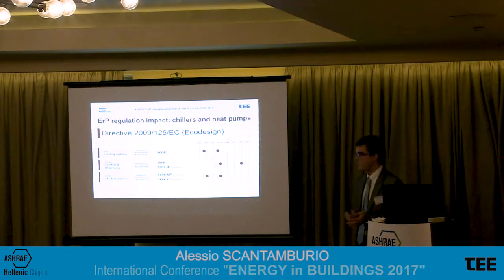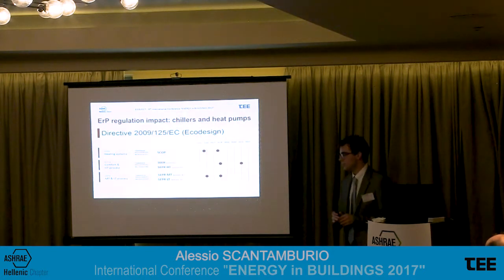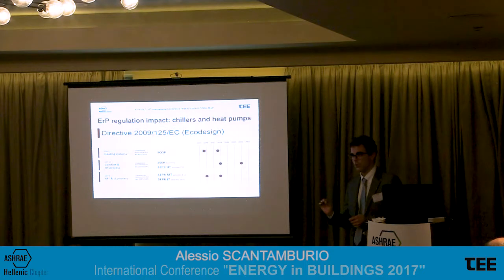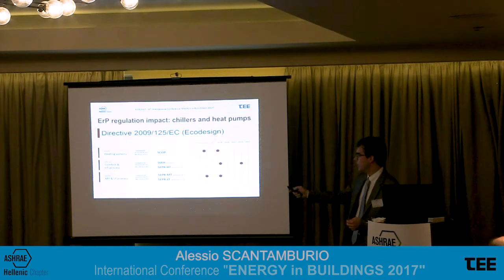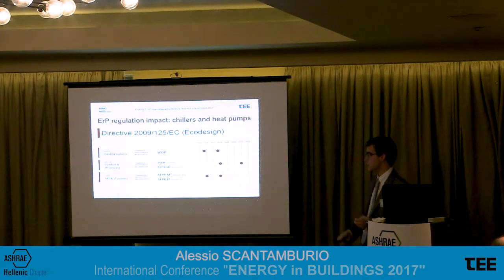One really important thing: each of these parameters is considered as a seasonal efficiency, not full load efficiency, but seasonal efficiency. So the regulation stresses the concept of high seasonal efficiency in the unit. So for heating systems, the parameter to comply with is the SCOP, seasonal COP.